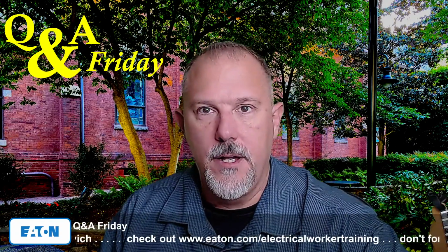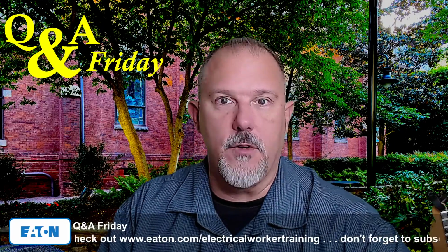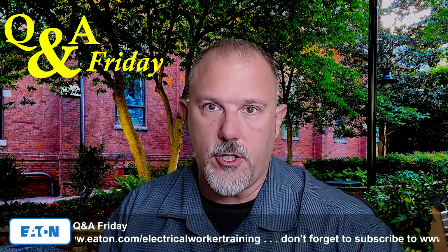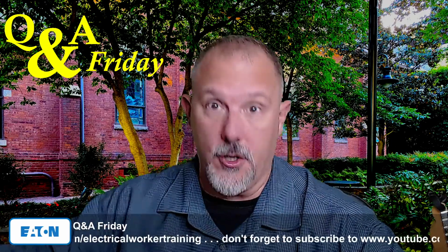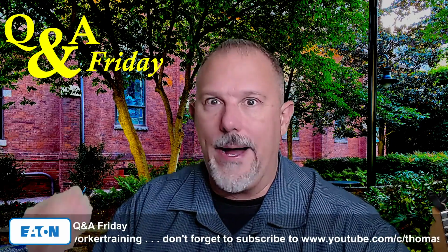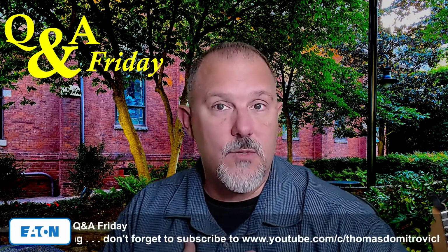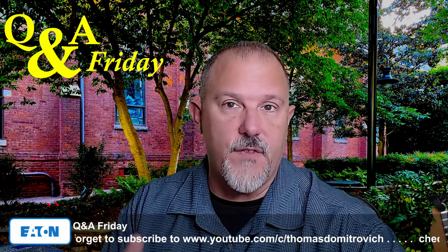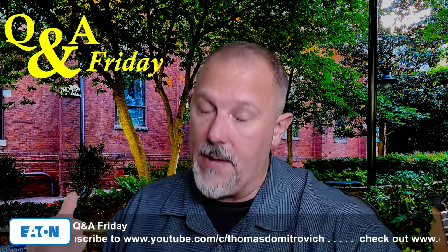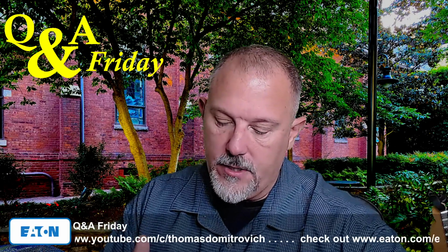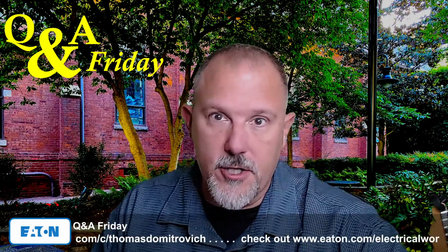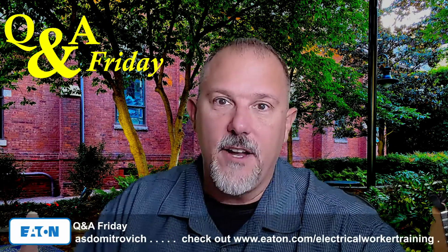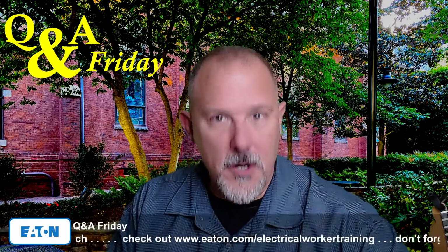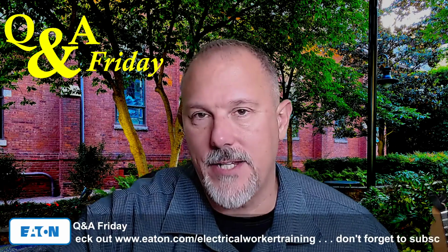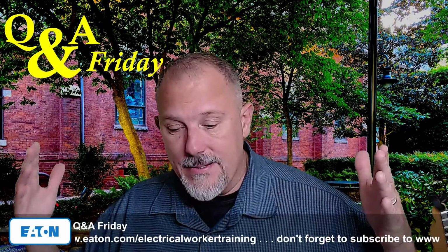My opinion was fault current is a general term like an overcurrent. A fault current can be an arcing fault current. It can be a bolted short circuit current. It can be a ground fault current. All of those go outside of the normal path. That's what I wanted to see in the code, that fault current was defined as any current outside of the normal path. And then you have fault current, available short circuit current. You have arcing fault current. So you have short circuit and arcing, and that would align with how we use it in the code. But it didn't go that way.